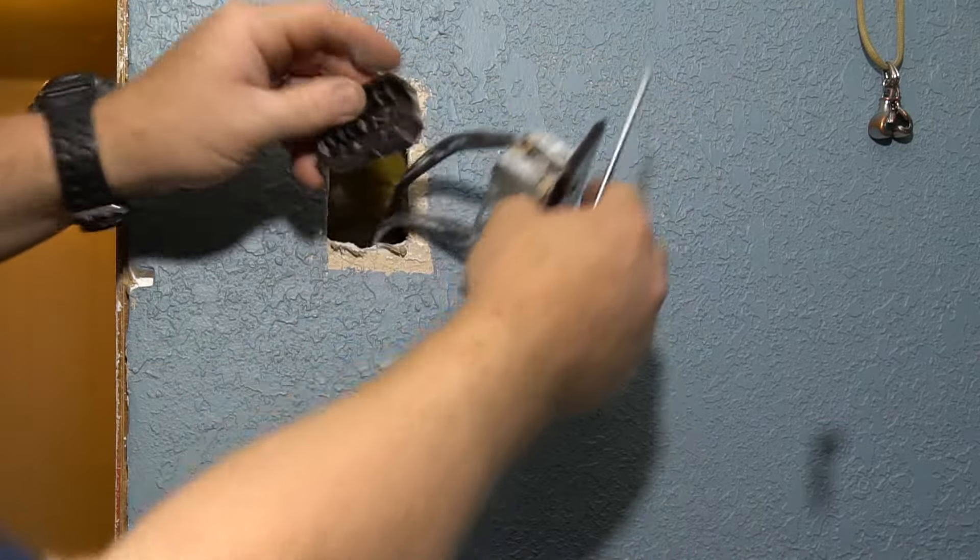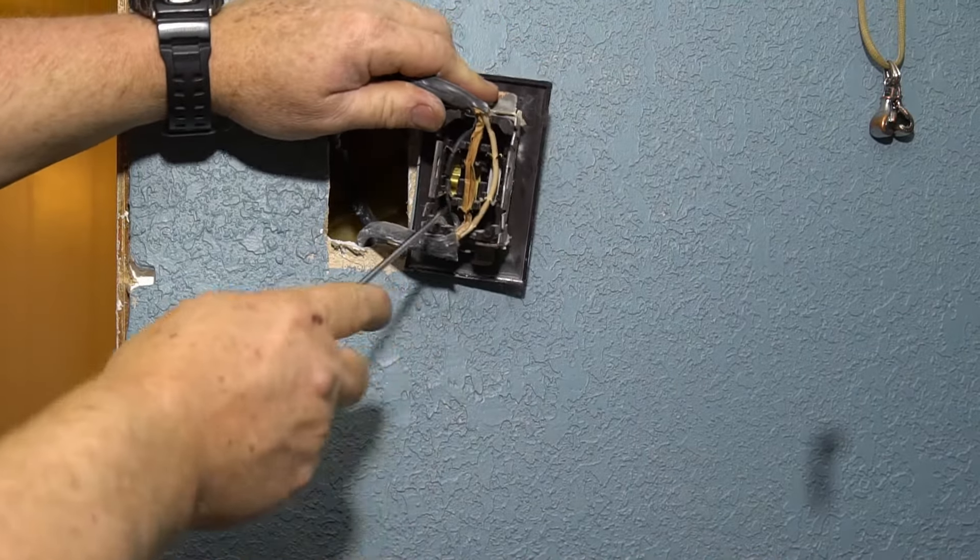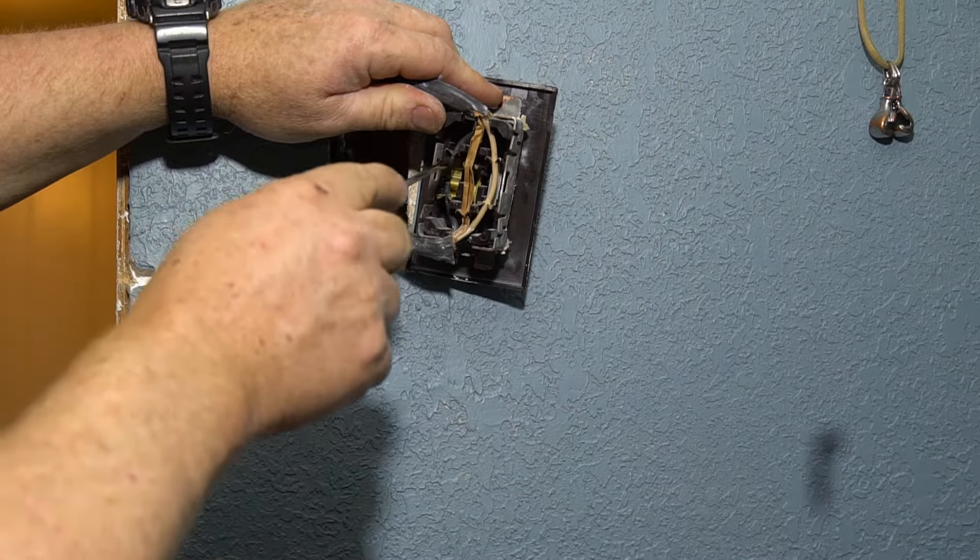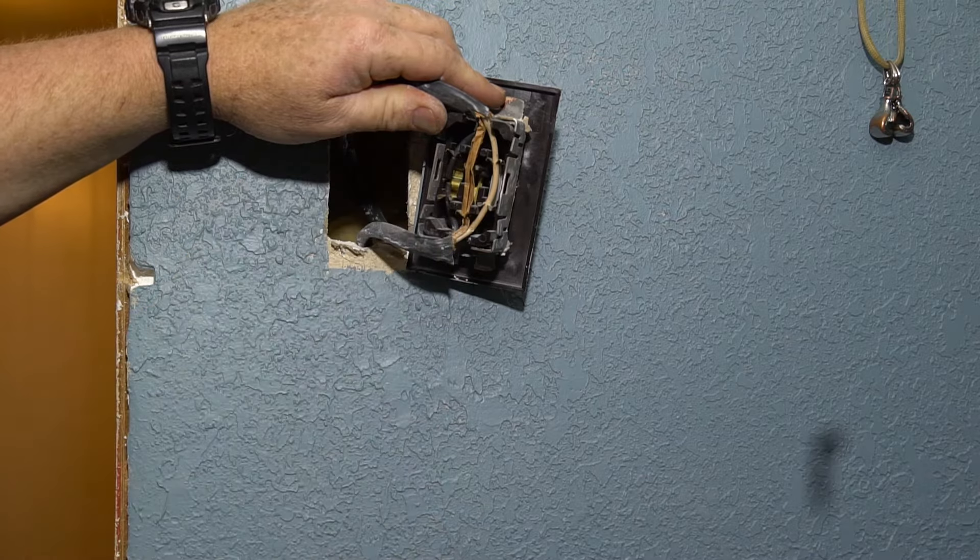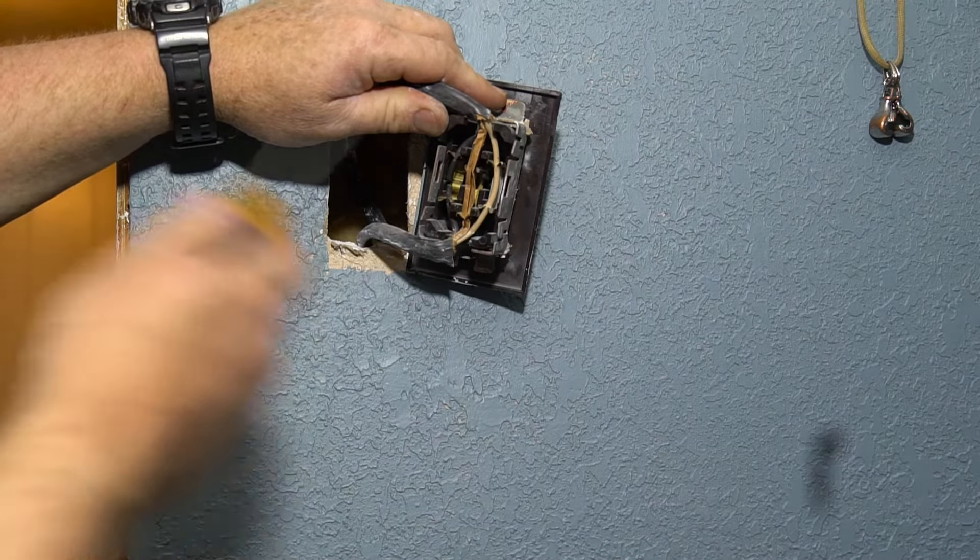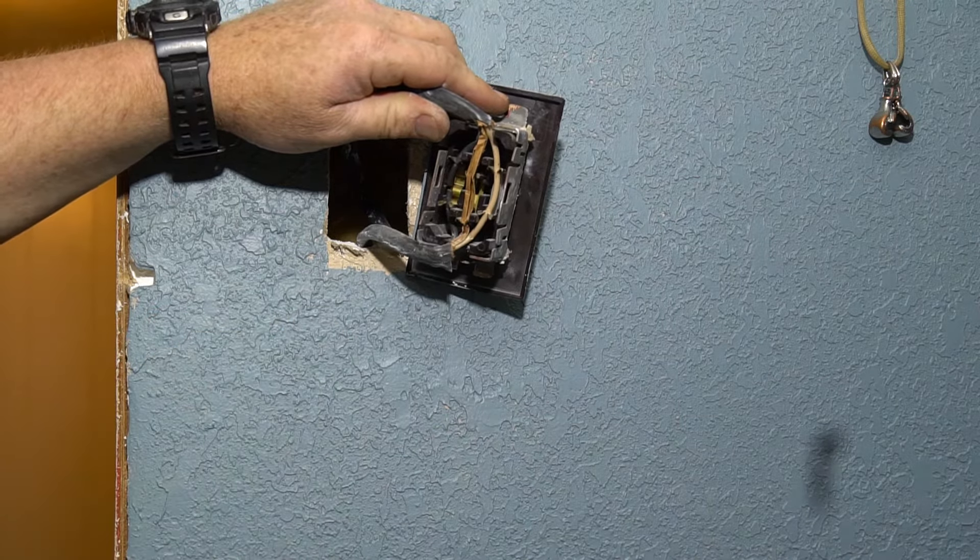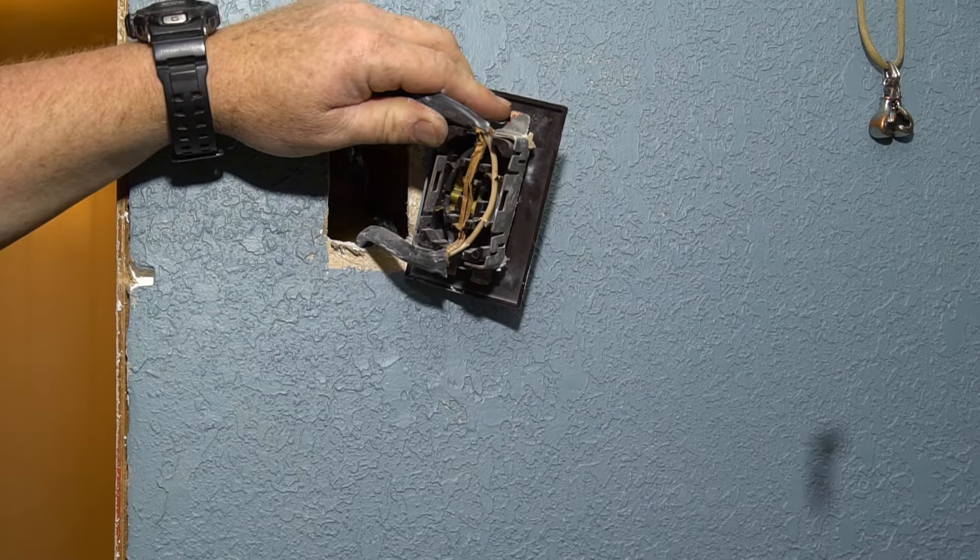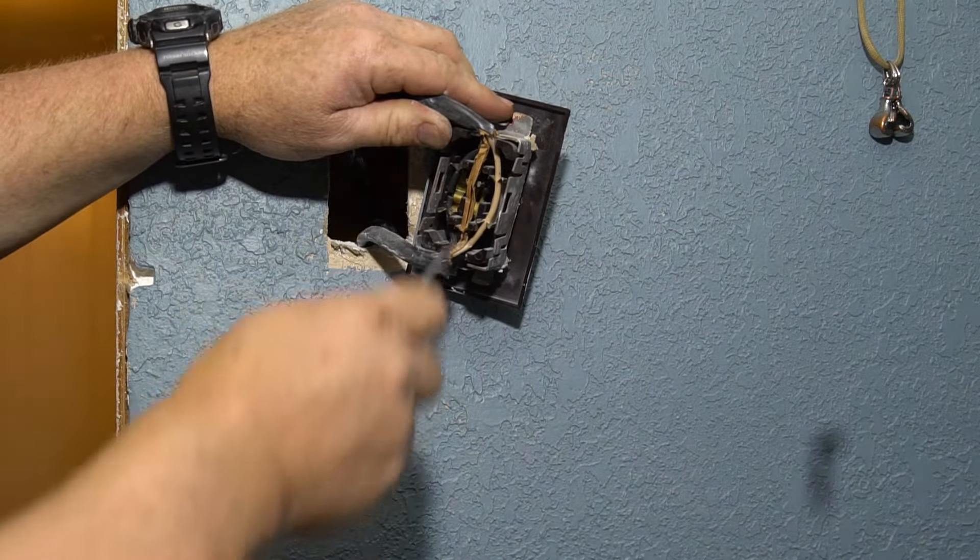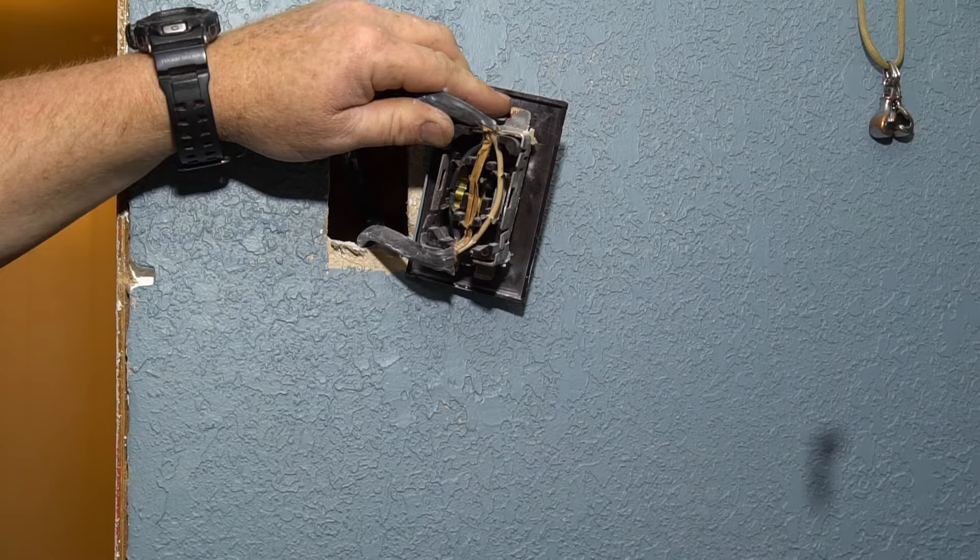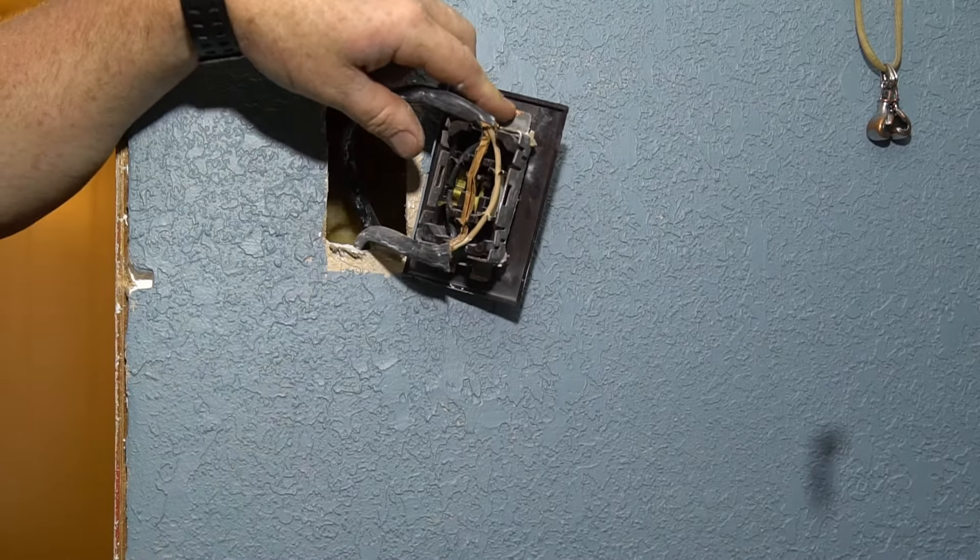All right, now let me get this thing turned around. As you can see here, they don't do any wiring, basically they just take the strip, the main coating off and just ram the wires down in there to make the connection. And it just is not a really reliable connection. It works for lights and okay, but after a while because it's not actually wired in and stripped and got that pressure, it's just making contact right there. Sometimes it can get a loose connection and it can cause a short, possibly lead into a fire, so I don't really like these things.